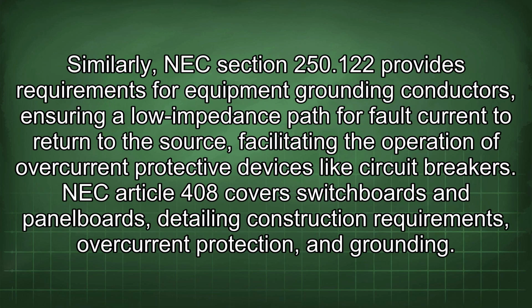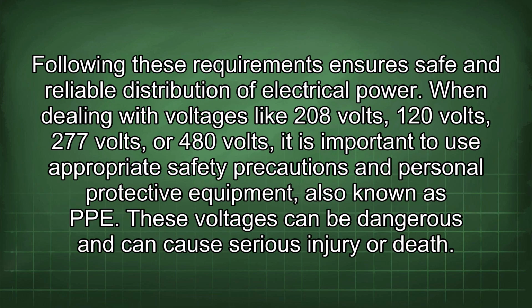Similarly, NEC Section 250.122 provides requirements for equipment grounding conductors, ensuring a low impedance path for fault current to return to the source, facilitating the operation of overcurrent protective devices like circuit breakers. NEC Article 408 covers switchboards and panelboards, detailing construction requirements, overcurrent protection, and grounding. Following these requirements ensures safe and reliable distribution of electrical power.